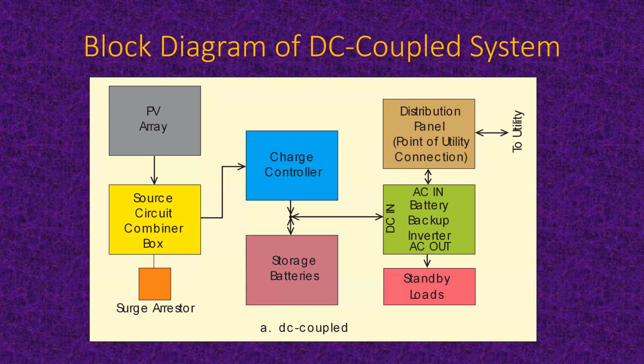We have a source circuit combiner box, because PV arrays typically come down 3 or 4 or more circuits from the roof, and they're combined together. So you've got a bunch of thin wires being combined so that the output of that source circuit combiner box is a set of fatter wires, maybe somewhere in the range from 8 to 6 to 4, depending on how many kilowatts you've got up there. And likely you'll have a surge arrestor at the input in case any lightning strikes anywhere near the array. You want to protect your equipment.